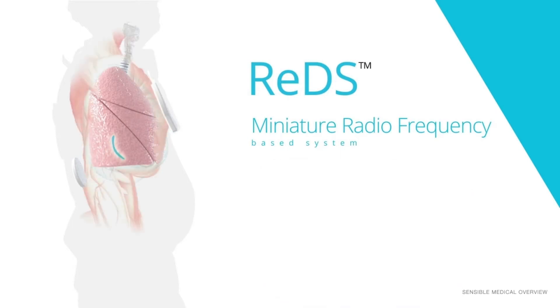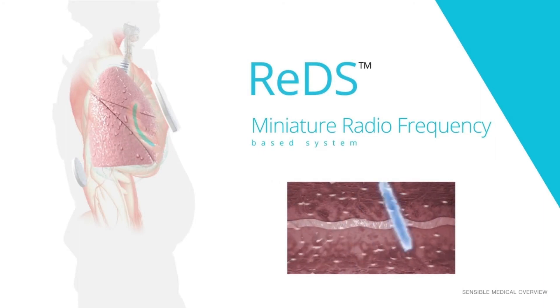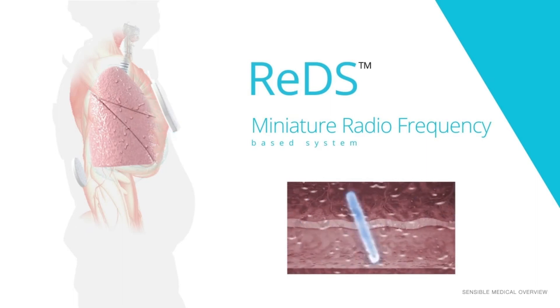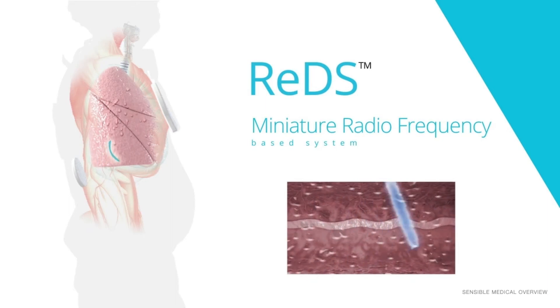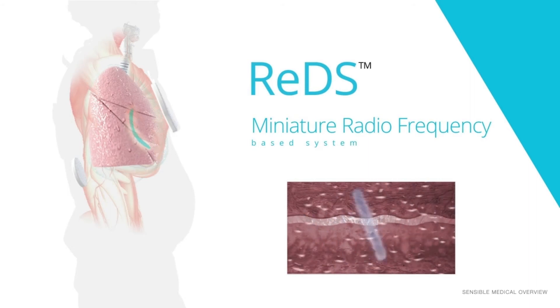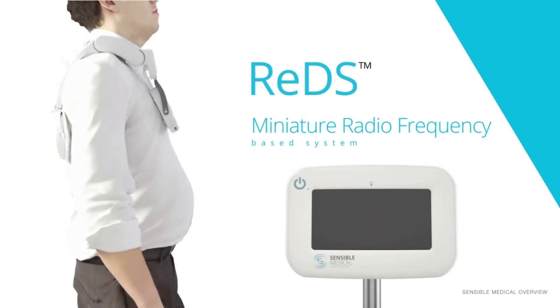Dry tissues, such as fat and bone and air, are transparent. The wave's speed and power are greatly affected by the amount of fluid in the tissue it passes through. It will travel slower and become weaker the more fluid. By measuring the travel time and power levels at the receiving sensor, REDS can directly and accurately measure the fluid content in the tissue.